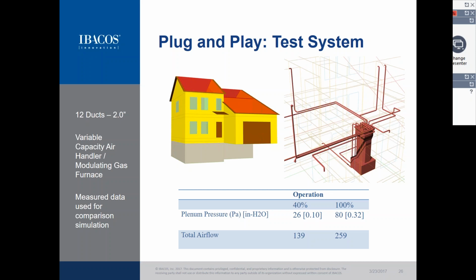So the house was tested primarily through the heating season using a modulating capacity. This is a 16,000 BTU capacity gas furnace. And you can see a rendering on the right of the approximate duct layout. The measured data was then used for comparison to the simulations, and so we measured things such as the exterior conditions and also the temperature within each room and the temperature at the discharge of each duct, as well as a number of specific components on the actual air handler, again, to really fully understand the performance so that we could compare it to these simulations.